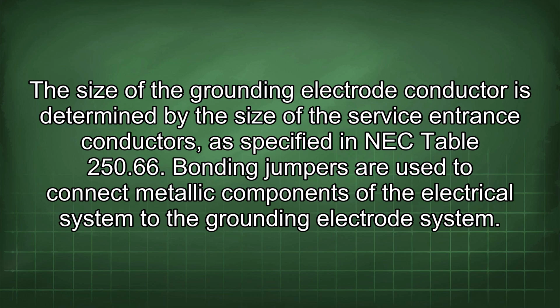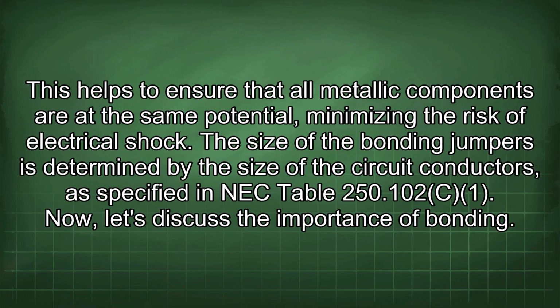250.66. Bonding jumpers are used to connect metallic components of the electrical system to the grounding electrode system. This helps to ensure that all metallic components are at the same potential, minimizing the risk of electrical shock. The size of the bonding jumpers is determined by the size of the circuit conductors, as specified in NEC Table 250.102. Now let's discuss the importance of bonding.